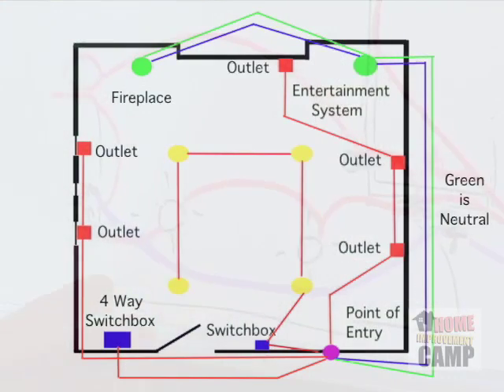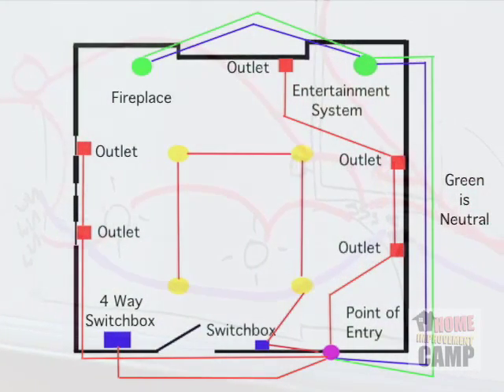So we've got our three circuits - our red circuit, our blue circuit, and our green circuit. Those are going to be home runs back to the circuit breaker panel. We've got something else here too - a purple line. That's going to be our four-way switch. It's going to start out with a three-way switch, go to a four-way switch, then to another three-way switch.